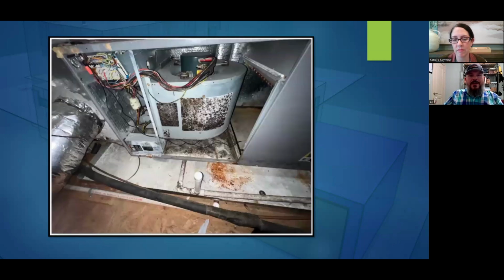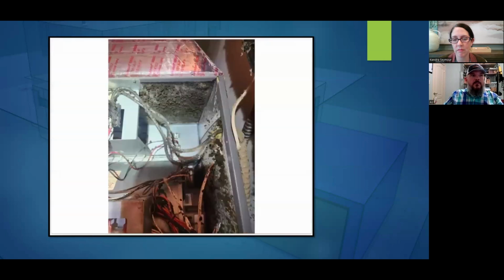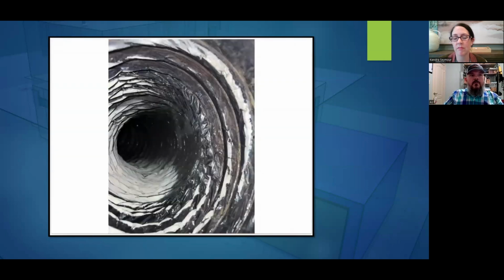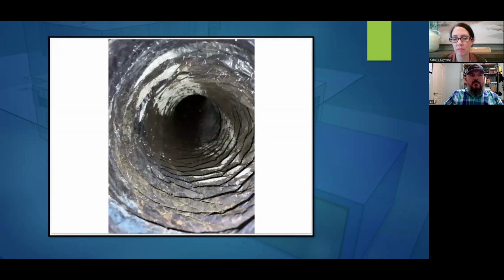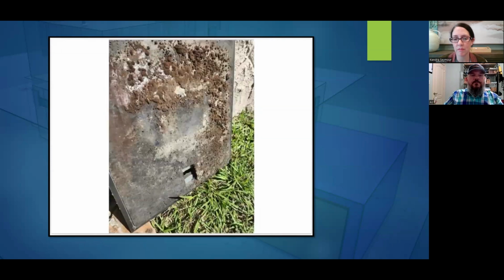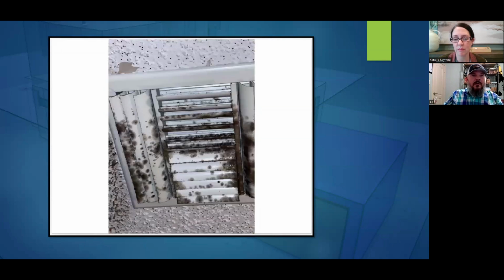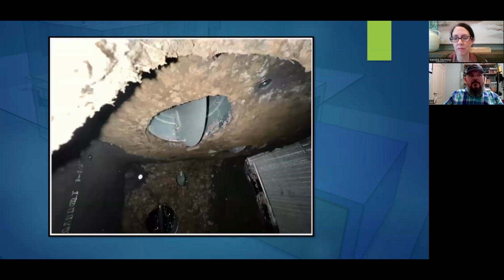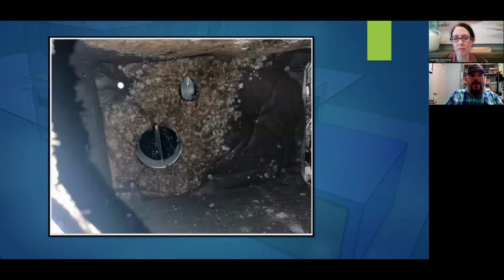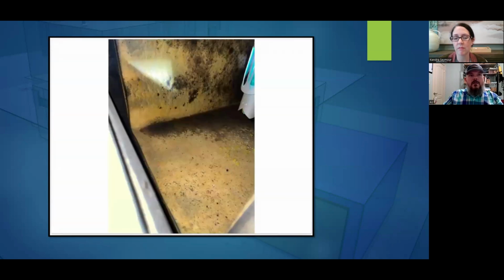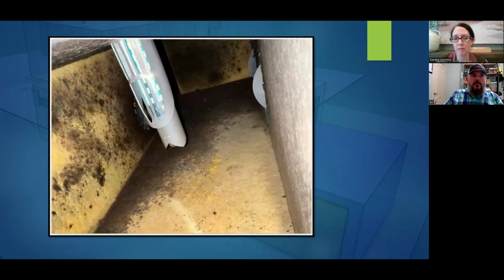These units must be completely disassembled. To remove the coil will require fully recovering refrigerant from the system. That's a pretty involved process. The entire system must be meticulously cleaned, manually agitated, scrubbed, and wiped out with the proper cleaners.